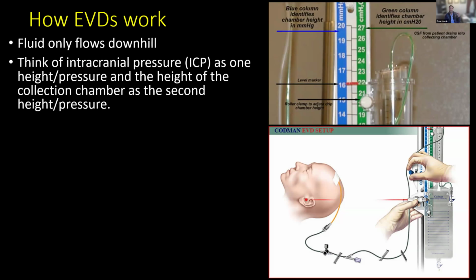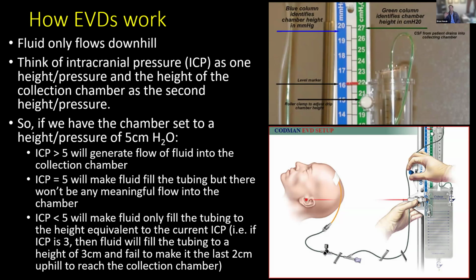And so if we think of intracranial pressure, the pressure inside the baby's head, as one height or pressure, and then we think of how high we put that collection chamber relative to the head as the second height or pressure, fluid is only going to flow into that collection chamber when the pressure in the head is in excess of the height of that collection chamber. So let's say we set the collection chamber to 5 centimeters of water, meaning it's set 5 centimeters above the patient's external auditory meatus, above their ear hole. If their ICP is greater than 5, fluid's going to flow up that little 5 centimeter hill and down into the collection chamber. If their ICP equals 5, fluid's going to make it almost to the top of the hill. It'll be sitting right at the top of the hill, but there won't be any meaningful flow. And if their ICP is less than 5, then the fluid won't make it up that little hill to get into the collection chamber. So if their ICP was 3, then the fluid would make it 3 centimeters of the way up, but it wouldn't quite make it that last 2 centimeters to get over the hump and into the collection chamber. So it's really simple in terms of mechanics.